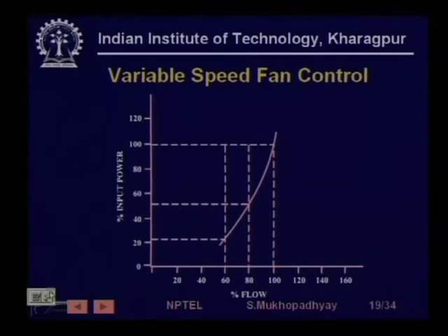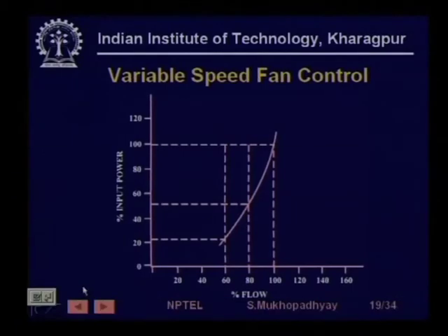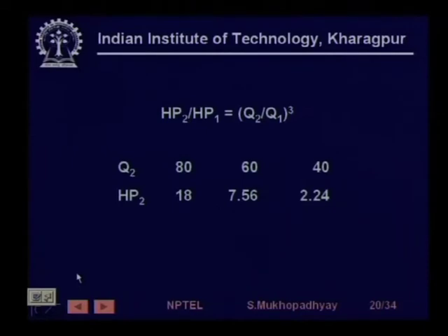So, this is the essence of energy. This shows how energy saving a variable speed drive can be, and just to drive the point home, we are going to show you that we are just applying that same formula. Remember that at Q1 equal to 100 we had a HP requirement of 35 HP.